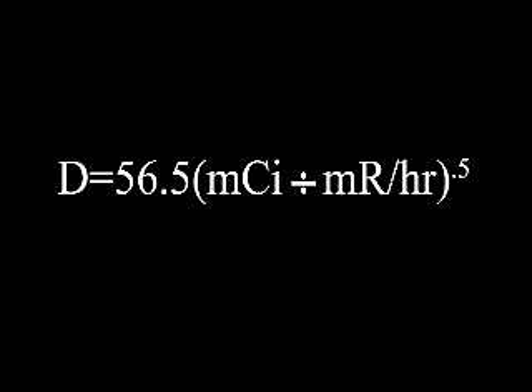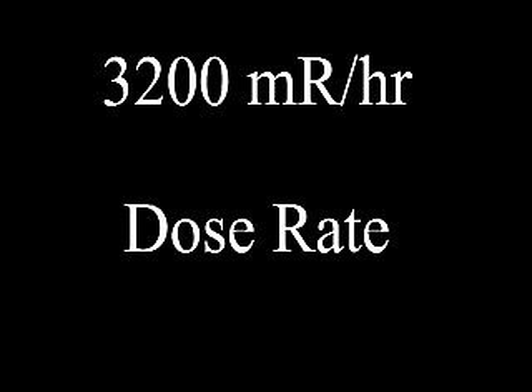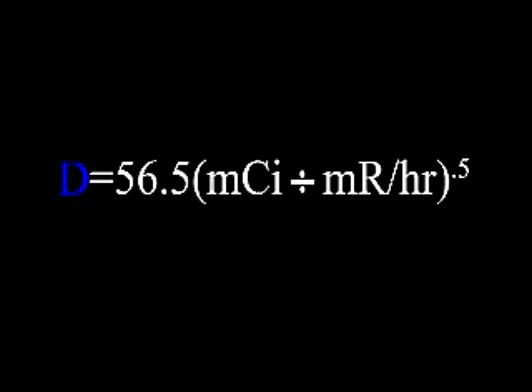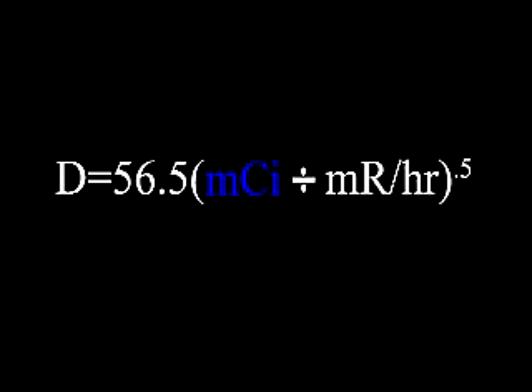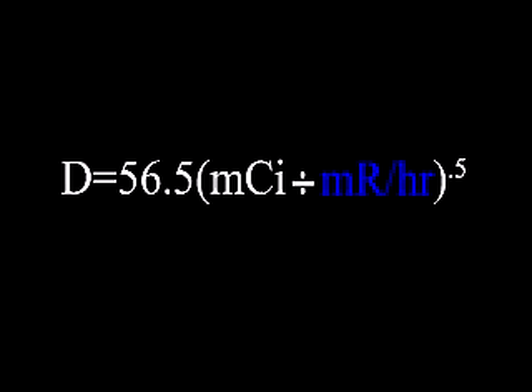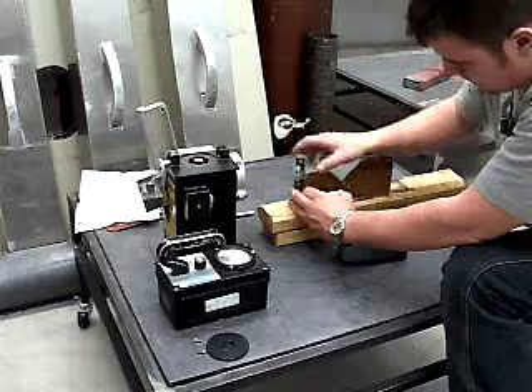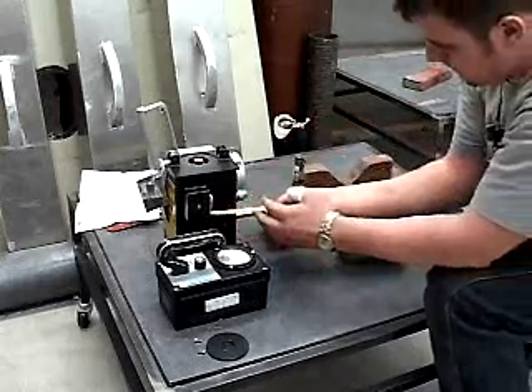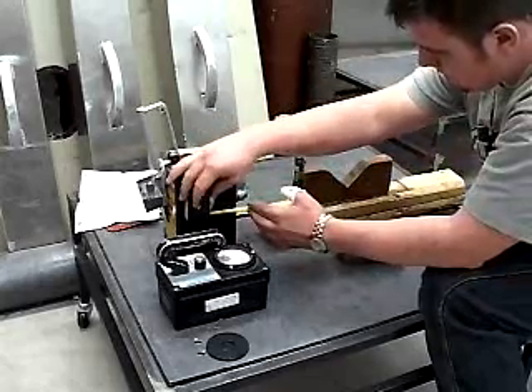To begin the process, the technician must calculate the distance in centimeters at which the actual dose rate from the calibrator source will provide 3200 mR per hour from the following equation. In this equation, D is the distance from the calibration source in centimeters, mCi is the source activity in millicuries, and mR per hour is the desired dose rate of the calibrator source in milliroentgens per hour. The calibrator source is placed at the calculated distance from the dosimeter.